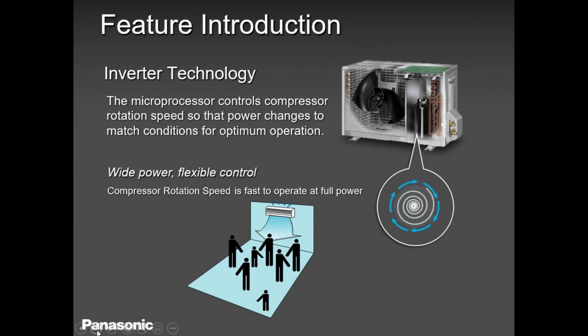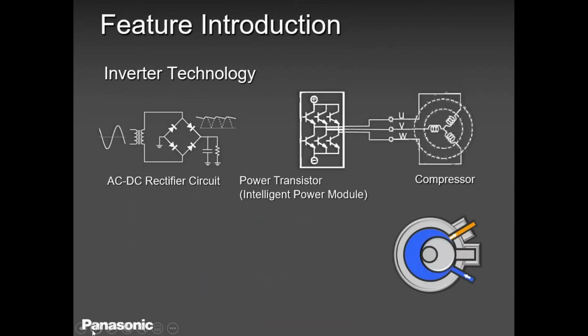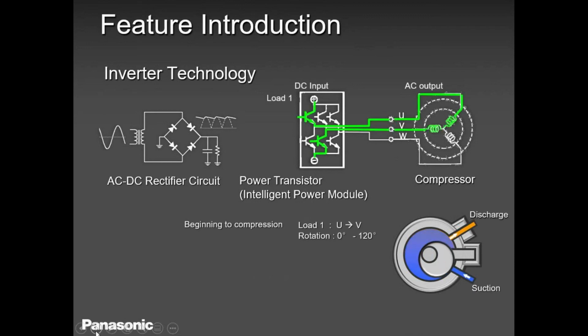So we have the horizontal and the vertical vanes, or some people call it flaps. It blows up and down based on your settings. Okay. So all our units, regardless, single zone, multi-zones, all our units, the compressors are inverter driven. So what is inverter driven? In a very simple term, it modulates based on the load. It goes up and down all the way from 28 hertz frequency all the way to 90, 98, 100, and comes down. Okay, depending on the load.